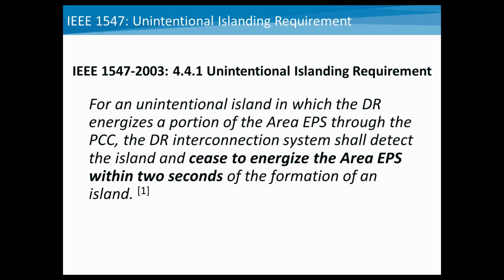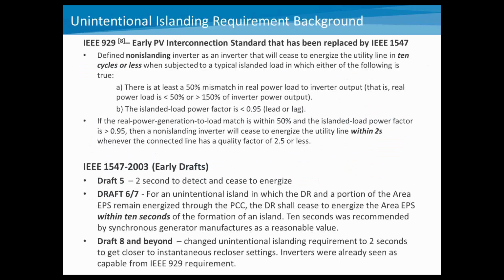So moving on to specific requirements around unintentional islanding. IEEE 1547, section 4.4.1, gives the unintentional islanding requirement. And it's stated here: for an unintentional island in which the DR energizes a portion of the area EPS through the PCC, the DR interconnection system shall detect the island and cease to energize the area EPS within 2 seconds of the formation of the island. So the key point here is realizing that it needs to detect and cease to energize within 2 seconds per the requirement.